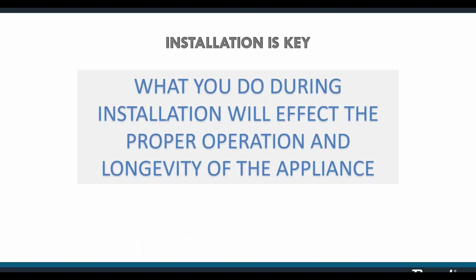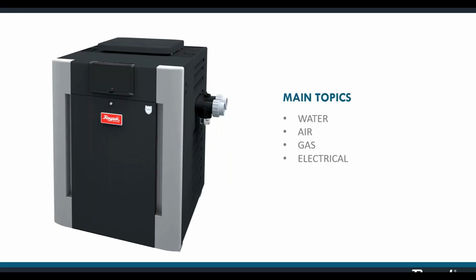This heater, and indeed any gas burning appliance, has certain requirements for proper operation. You need proper water flow rates, gas flow rates, combustion air, electrical input, correct ventilation, and more. If you install it wrong, it won't work right. A large percentage of the failure rates we see can be attributed to substandard installation. A properly installed heater works better and lasts longer, and that keeps your customers happy.